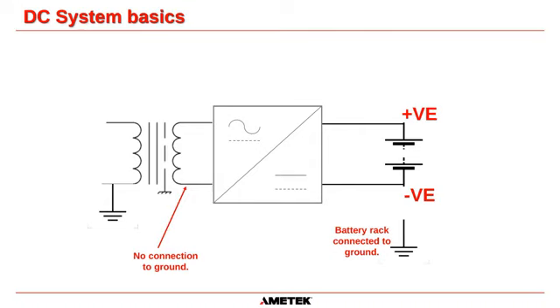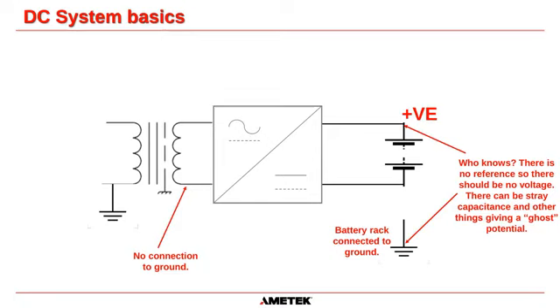So that is why we have floating battery systems, to make it safe for technicians to work on without having to isolate the battery. And just to reiterate, if we took a Fluke and went between the positive of the battery down to ground on DC voltage, there should be no reference whatsoever. There can be stray capacitance and other things giving a ghost potential, as I said with the transformer, but in a very basic, rudimentary system that does not have ground fault detection on it, but does have an isolation transformer, there should be absolutely no reference between positive to ground or negative to ground.